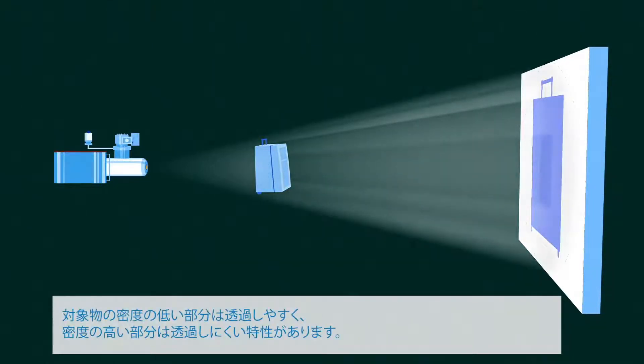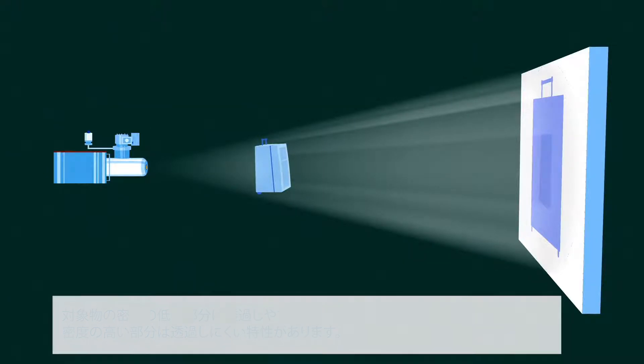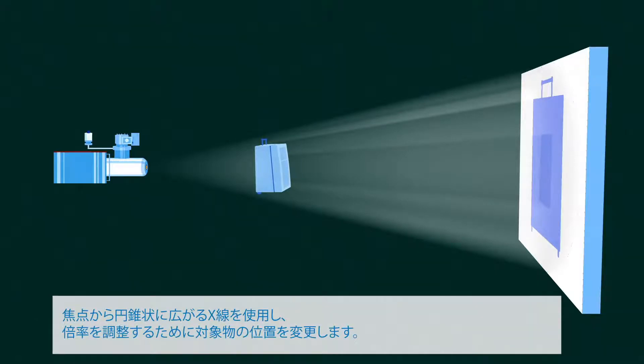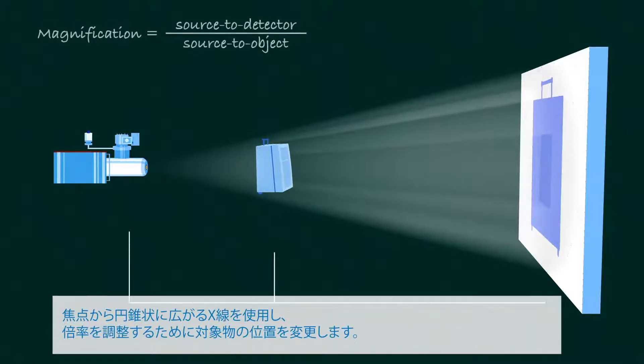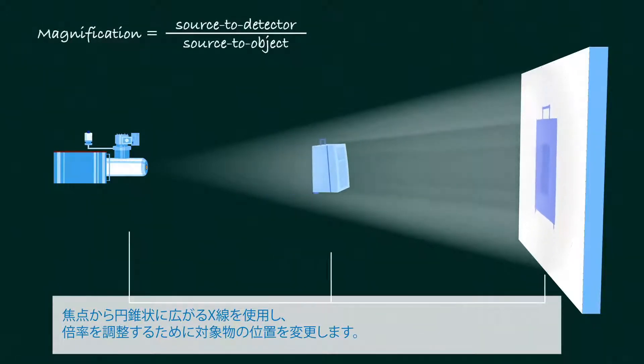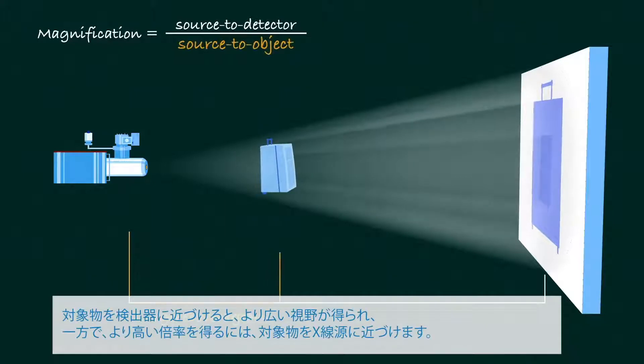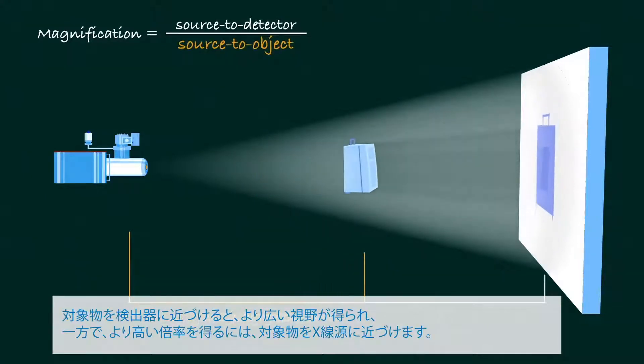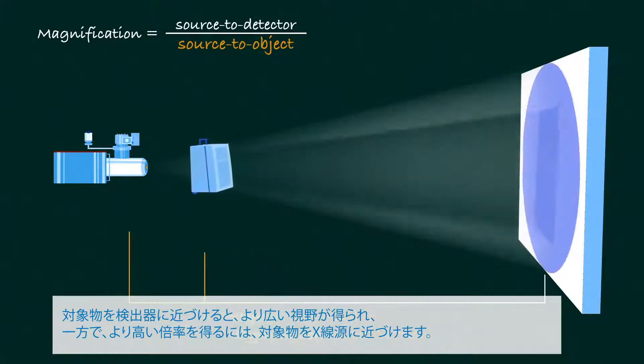Low-density volumes of the object allow high transmission, while high-density volumes allow low transmission. With a point X-ray source, magnification and illuminated volume can be adjusted. Larger coverage is achieved by moving the object closer to the detector, while higher magnification is achieved by moving the object closer to the source.